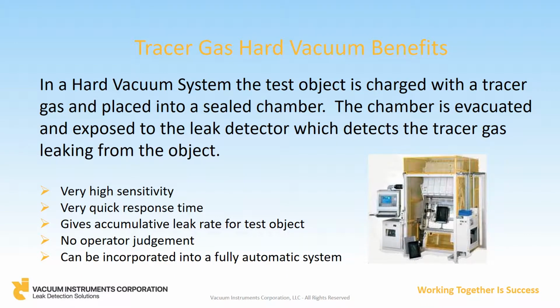Hard vacuum testing is by far the most sensitive and accurate leak testing method. Here, the object under test is placed into a vacuum-suitable chamber. As stated previously, the object will be evacuated and backfilled with helium gas to a preset pressure. The chamber will also be evacuated to a level on the order of 50 to 200 microns. Once the vacuum level in the chamber has been achieved, the leak detector will sample the environment of the chamber. The advantage of sampling under vacuum is a much higher degree of sensitivity, as well as an enhanced signal-to-noise ratio, providing the highest level of repeatability.